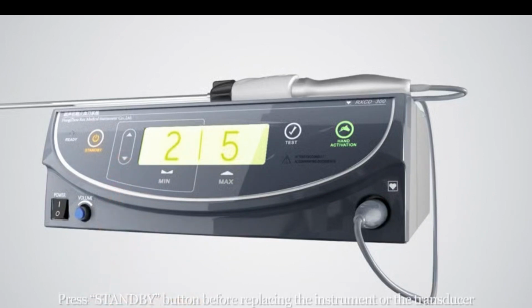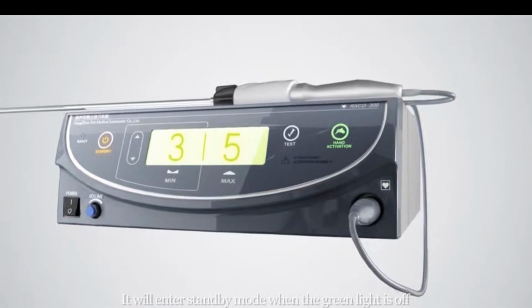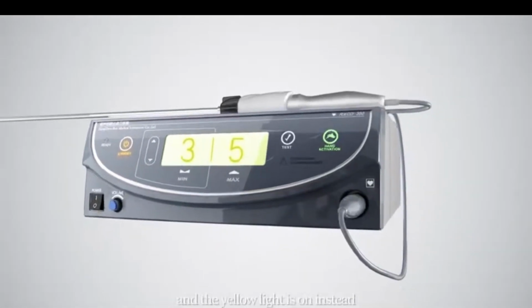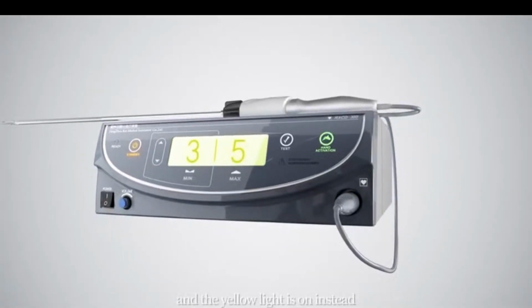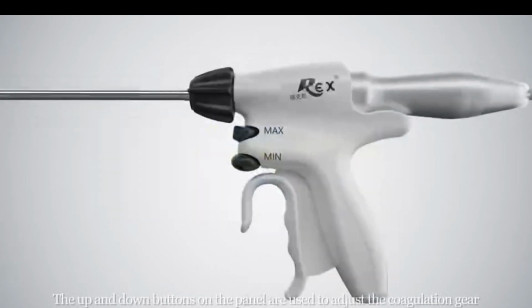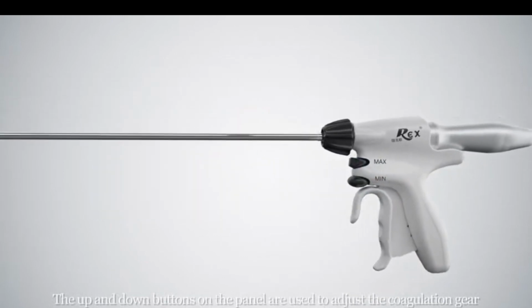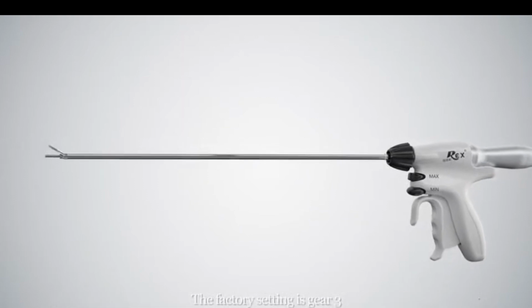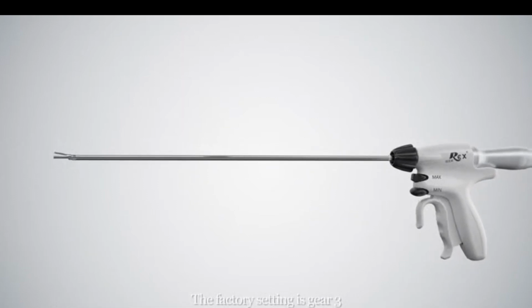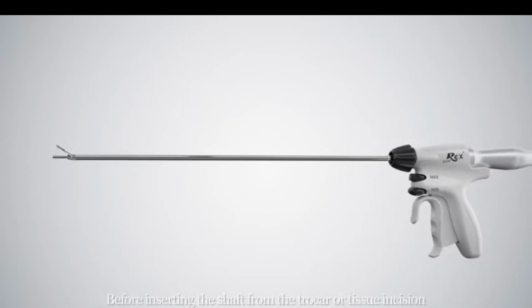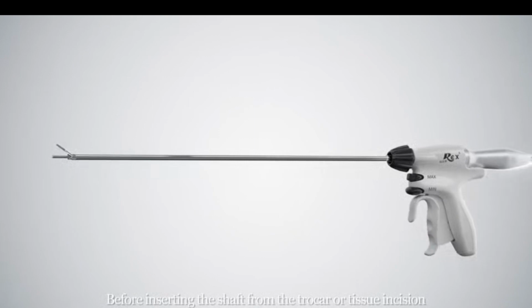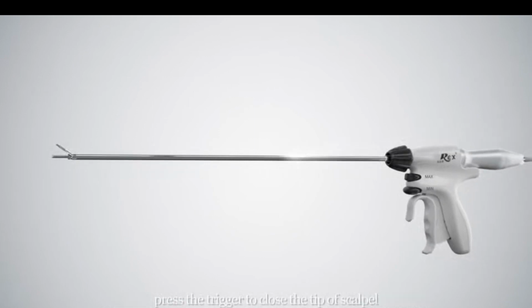Press the standby button before replacing the instrument or the transducer. It will enter standby mode when the green light is off and the yellow light is on instead. The up and down buttons on the panel are used to adjust the coagulation gear. The factory setting is Gear 3. Before inserting the shaft from the trocar or tissue incision, press the trigger to close the tip of the scalpel.